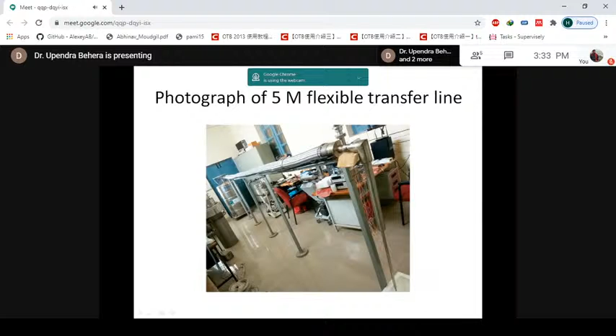This is the cool down and warm up curve for this 5-meter flexible transfer line. We have put sensors at every 0.5 meter interval, and these are the 3 data points taken - at the inlet, one at the middle, that is 2.5 meters from the end, and the other one at 4.5 meters from the inlet. So you can see that at the middle, as with the previous one we did for 3 meters, this is reaching the lowest temperature.